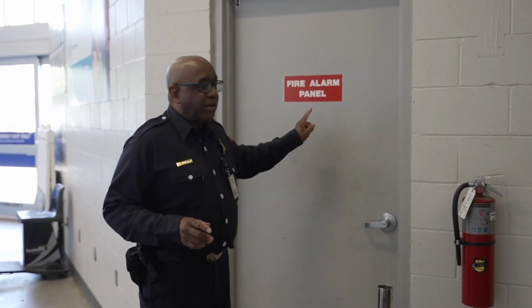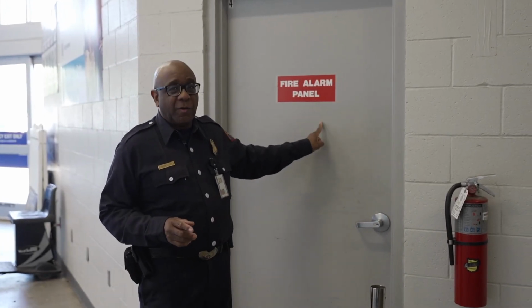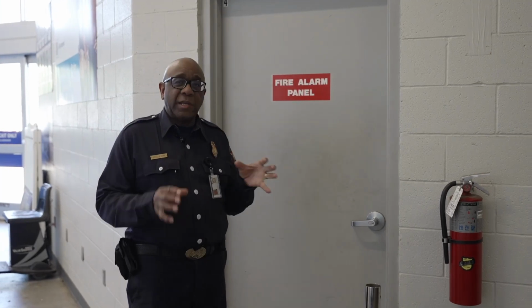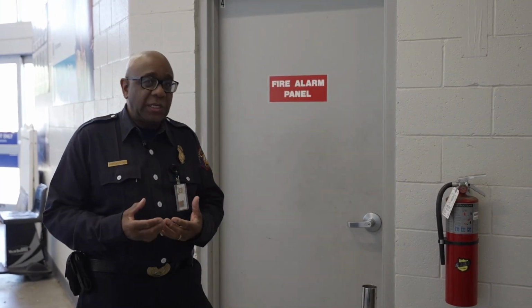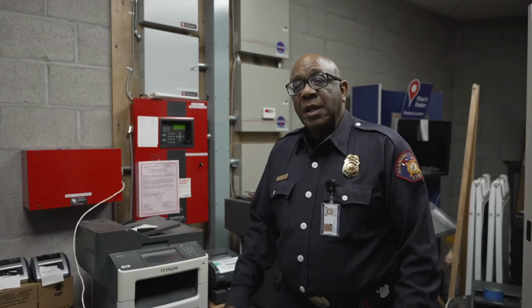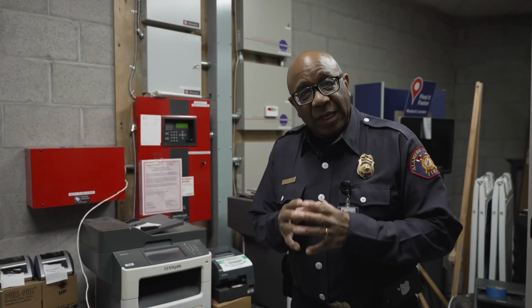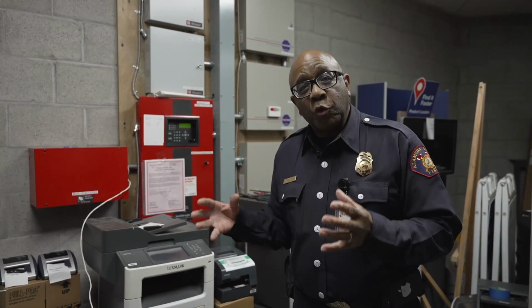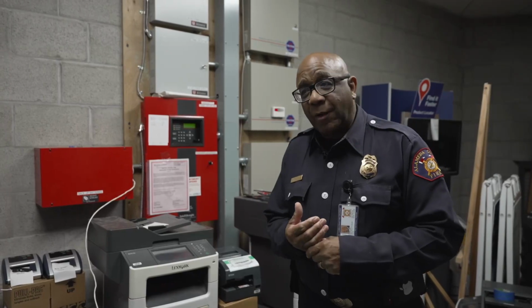All right, on the large mercantile, almost always you're going to find a full fire alarm system. In this case here, the room is marked fire alarm panel. We're going to go inside and look at some of the things that you'd be wanting to see for your inspection. So now we're inside the locked room that contains the fire alarm panel.